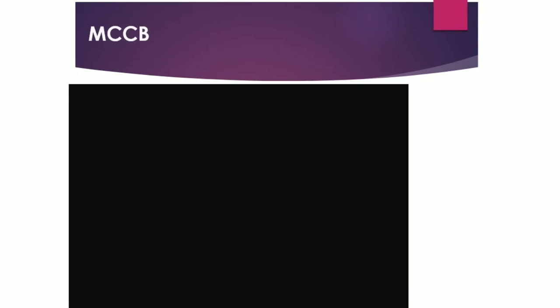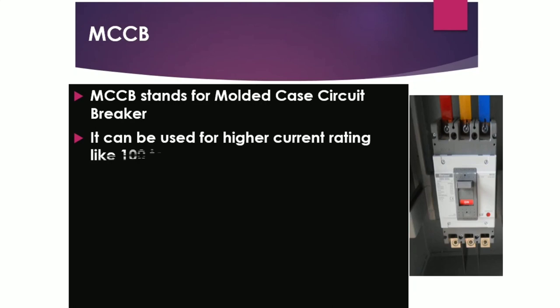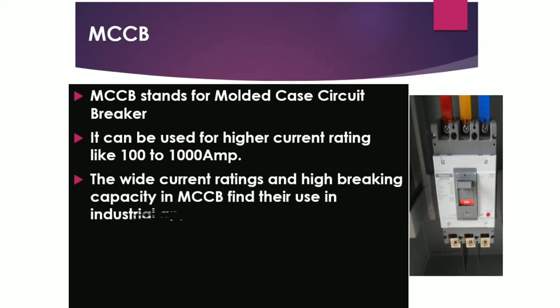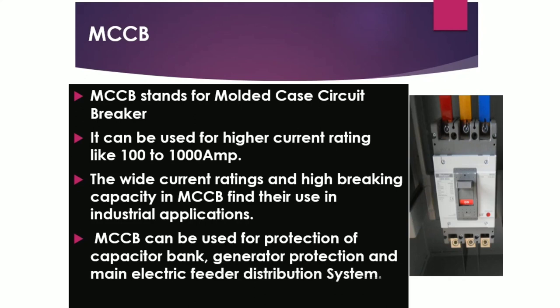MCCB stands for molded case circuit breaker. It is quite similar to the MCB but can be used for higher current ratings from 100 to 2000 ampere. With its wide current rating and high breaking capacity, MCCB finds uses in industrial applications such as protection of capacitor banks, generator protection, and main electric feeders in distribution systems.